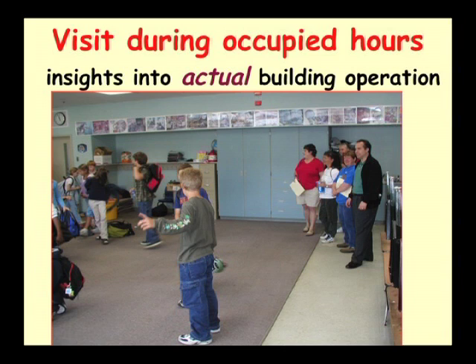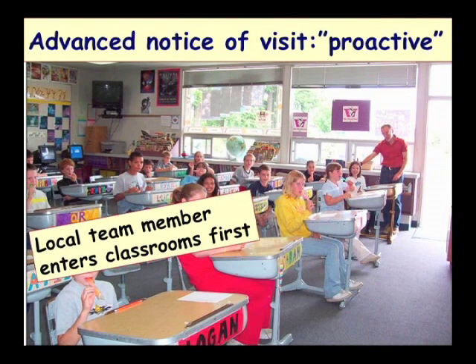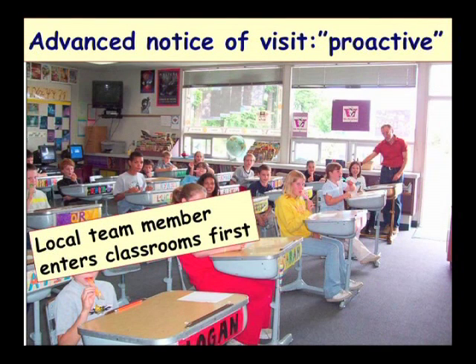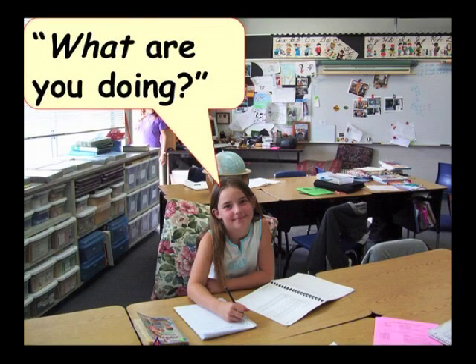We want to see schools during normal occupied hours at full capacity engaged in customary activities — we need the occupants' breath to do our carbon dioxide diagnostics of fresh air ventilation. We want staff to be warned well in advance that we're coming and that our walkthrough is routine, not in response to a crisis. That way we don't have to explain ourselves room by room. It's best for a local team member — a face the kids recognize — to enter the classroom first so we aren't just barging in with all our scary equipment, freaking out the little kids. Are you the ghostbusters? Should we hold our breath? Our typical answer is: we're trying to make sure you get plenty of fresh air in here.